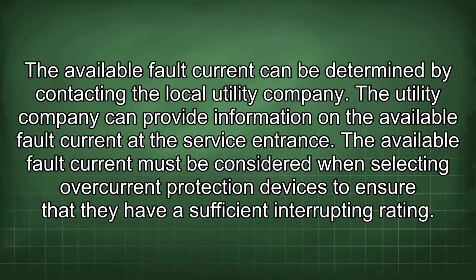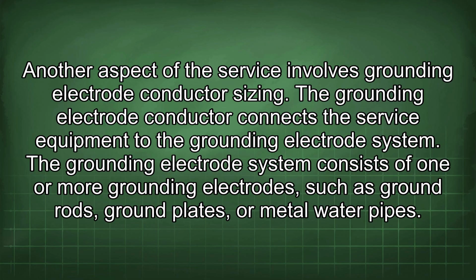The available fault current can be determined by contacting the local utility company. The utility company can provide information on the available fault current at the service entrance. The available fault current must be considered when selecting overcurrent protection devices to ensure that they have a sufficient interrupting rating. Another aspect of the service involves grounding electrode conductor sizing.